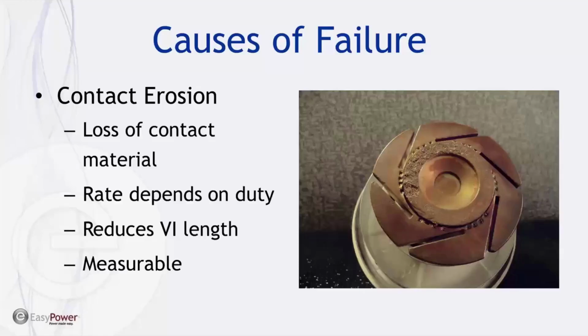And when the length of the VI is reduced, it reduces the wipe spring pressure, or closing force, of the vac interrupter. So at a certain point, if that wipe spring pressure is reduced too much, then the vac interrupter won't be able to hold itself closed if it were to see an increase in current. If that were the case, then you would have a failure, which could be catastrophic.